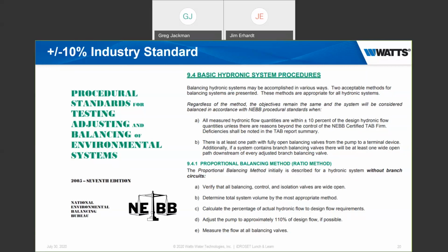Now, there might be some engineered systems that require 5%. What we found in our own testing in North Andover with our samples is that over a tremendous range of the valve, we are well within the 10%. It's really only when you get down to the minimum flow rates of the range in each valve size that we creep up toward that plus or minus 10%. But in the vast majority of the range of that valve, especially in the higher flow rates, we're well within 10%.